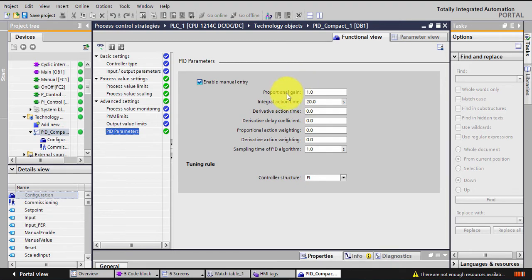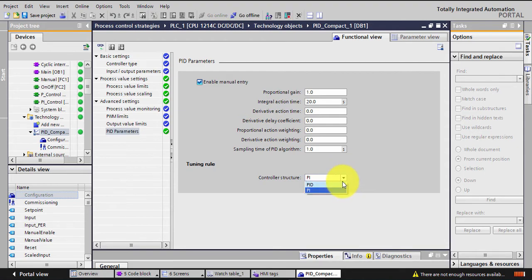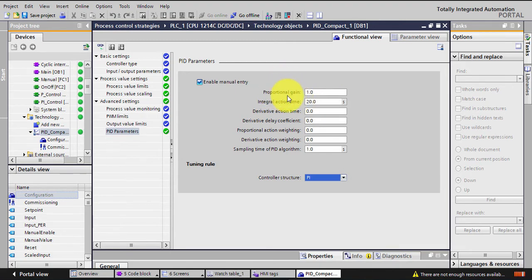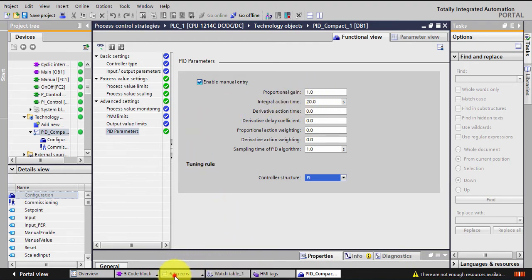Under PID parameters, I enabled manual entry. I'm looking for the proportional gain, the integral action time. From here you can also choose whether you want a PI or a PID — I chose to have a PI. So I want to enter the proportional gain number from the HMI.